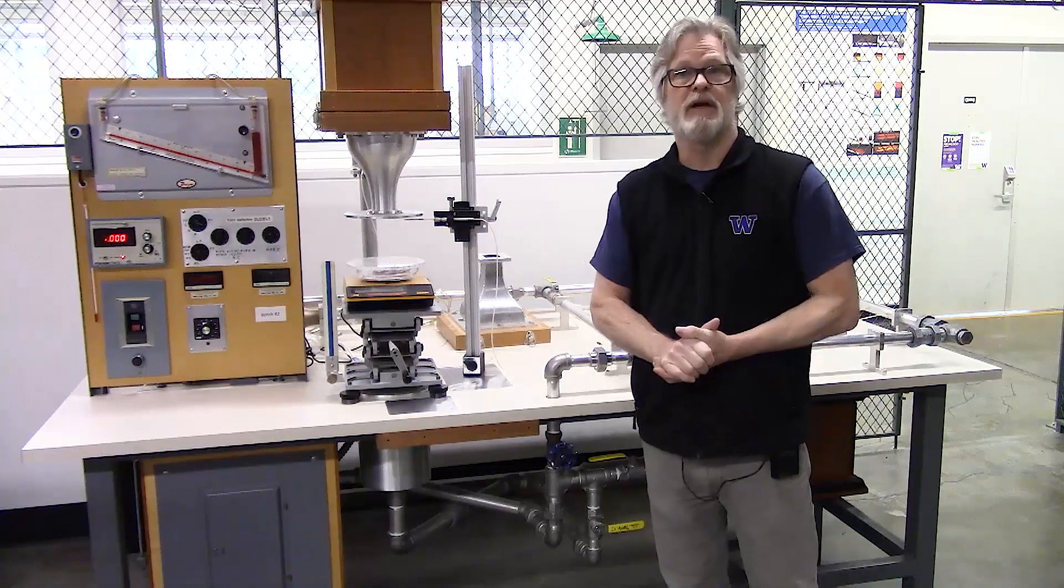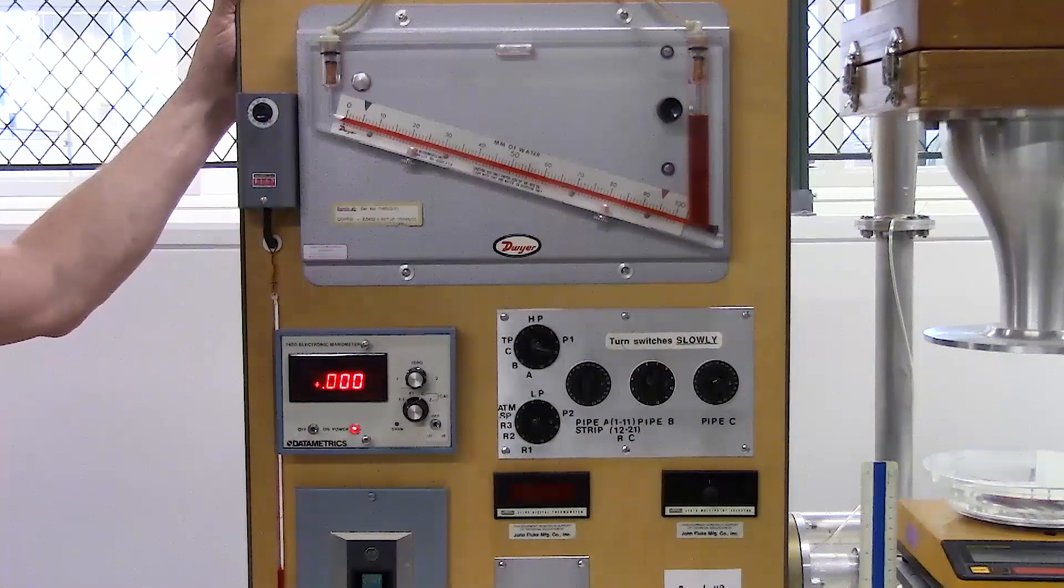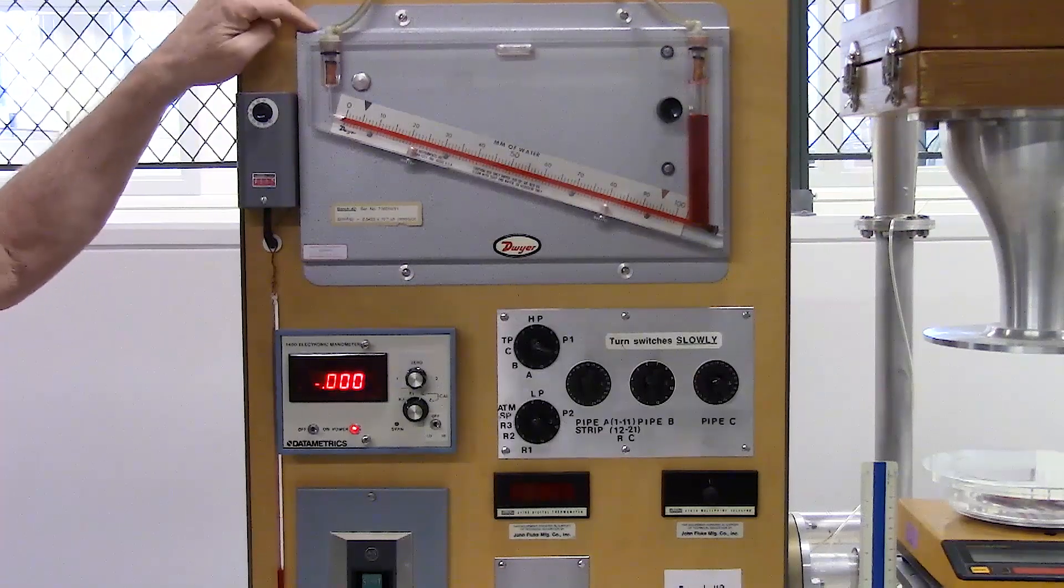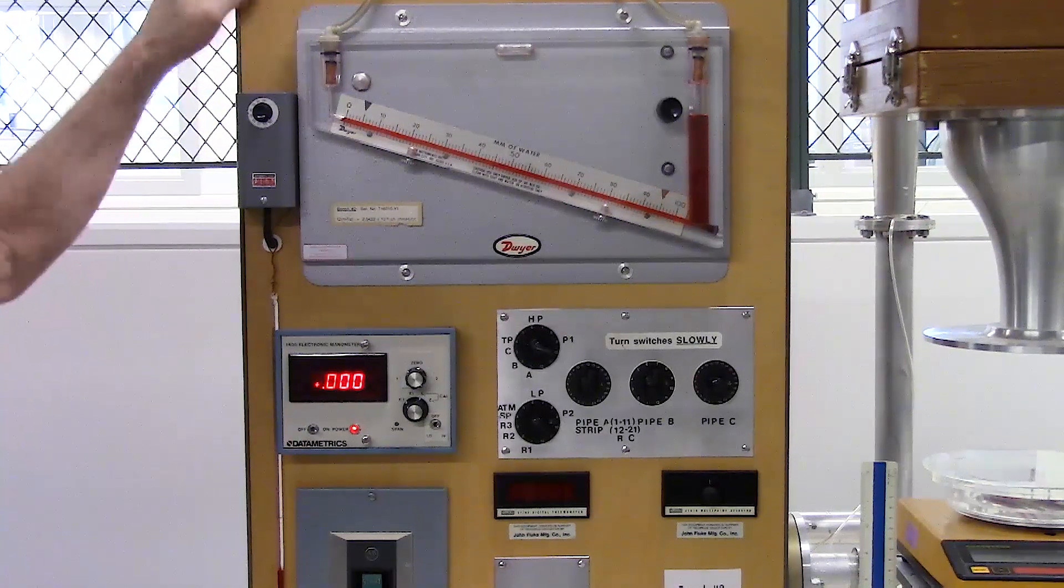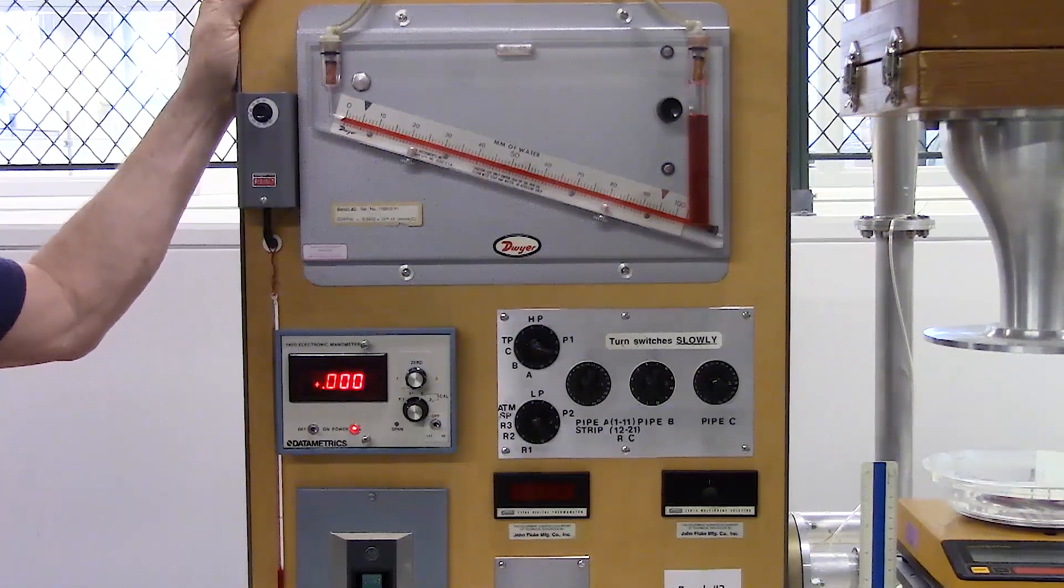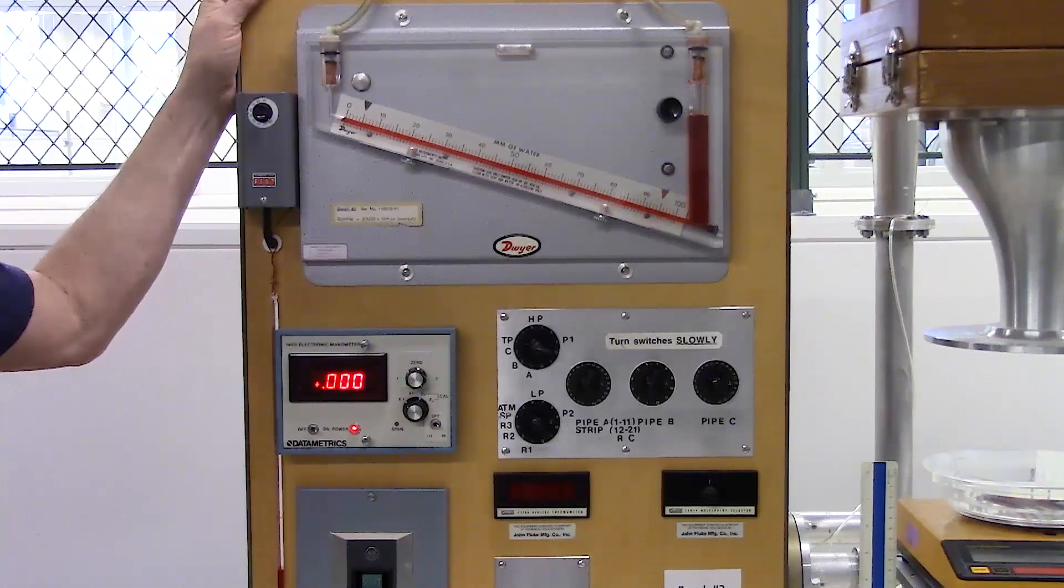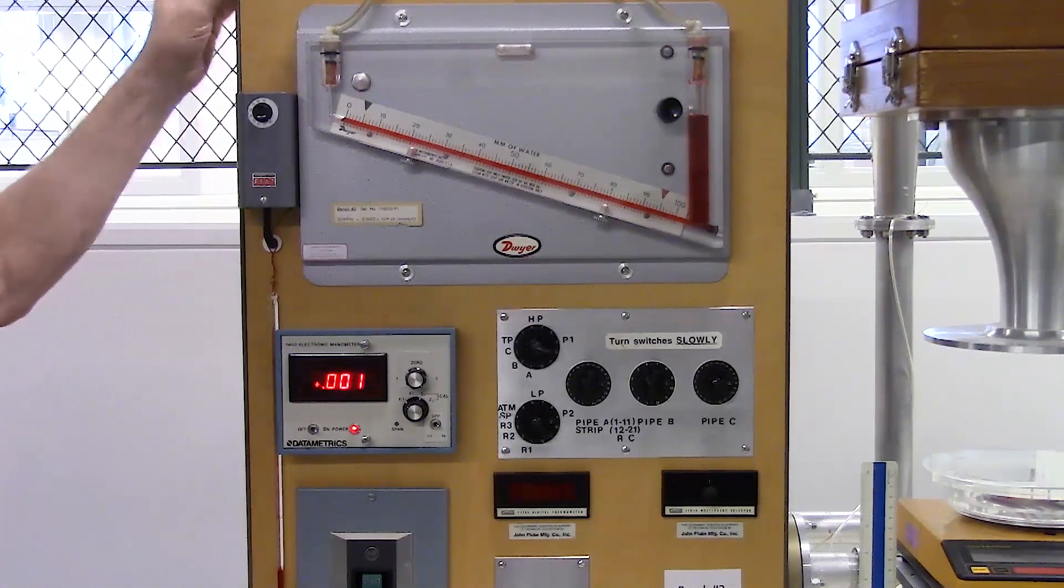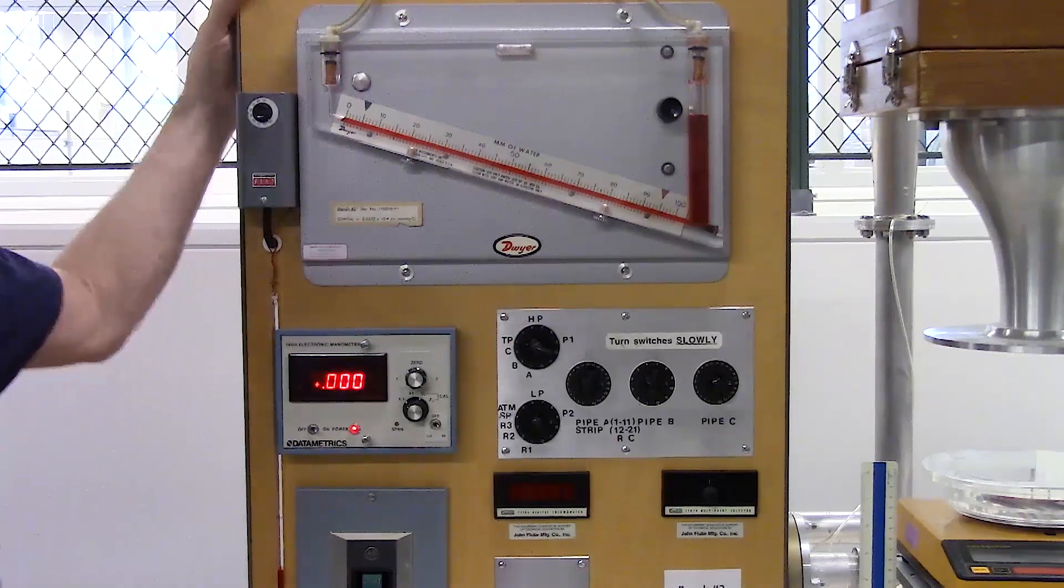Let's start with the instrument panel. To measure the flow through the system we have this incline manometer that's connected to either side of a laminar flow element. The pressure drop across the flow element is a measure of the volumetric flow rate in cubic meters per second and we can make that conversion using the calibration constant provided with the laminar flow element.